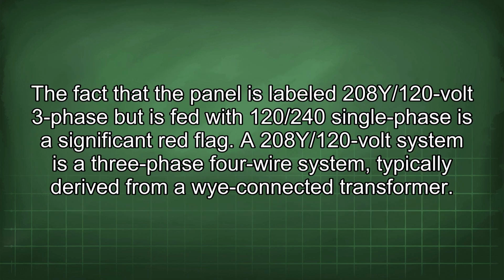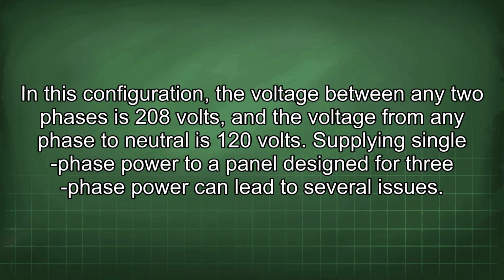The fact that the panel is labeled 208Y/120V 3-phase but is fed with 120/240 single-phase is a significant red flag. A 208Y/120V system is a 3-phase 4-wire system typically derived from a Y-connected transformer. In this configuration, the voltage between any 2 phases is 208 volts, and the voltage from any phase to neutral is 120 volts. Supplying single-phase power to a panel designed for 3-phase power can lead to several issues.